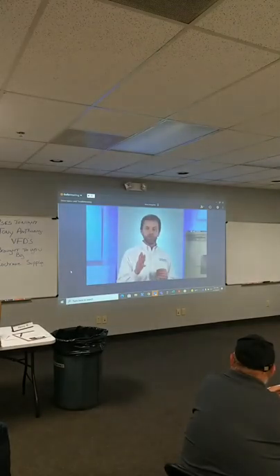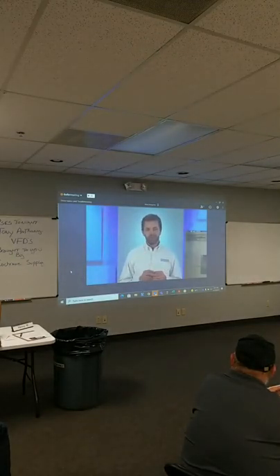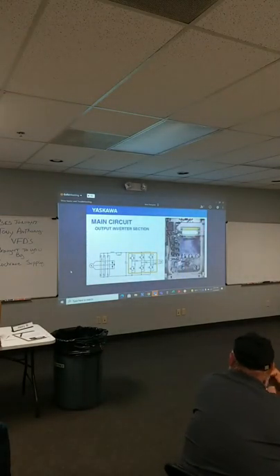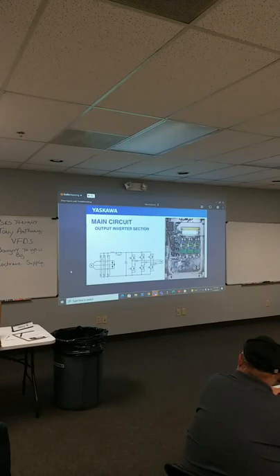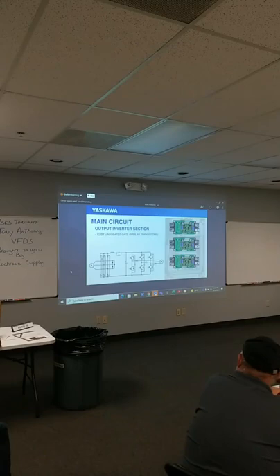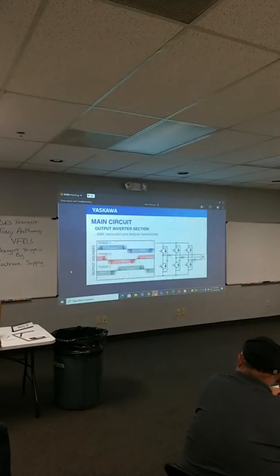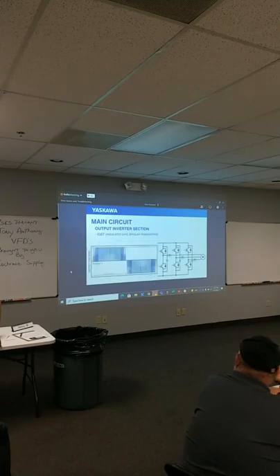We now move to the last major section of the drive, the output, or more specifically, the inverter section. The inverter section of the drive is comprised of IGBTs, which stands for insulated gate bipolar transistors. These work together to produce a simulated three-phase AC waveform for the motor. One IGBT will take power to build the upper part of the wave.